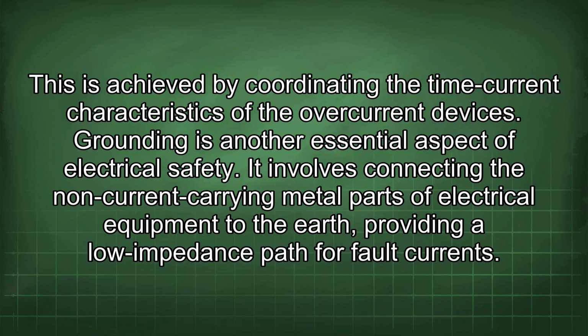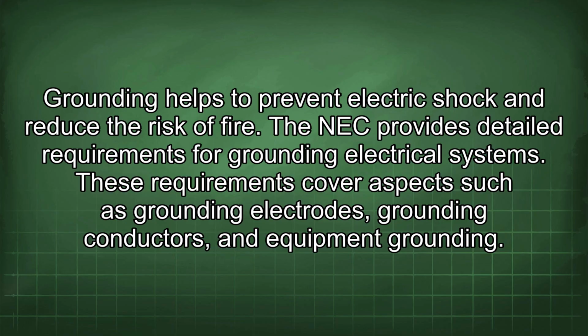It involves connecting the non-current carrying metal parts of electrical equipment to the earth, providing a low impedance path for fault currents. Grounding helps to prevent electric shock and reduce the risk of fire. The NEC provides detailed requirements for grounding electrical systems. These requirements cover aspects such as grounding electrodes, grounding conductors, and equipment grounding.